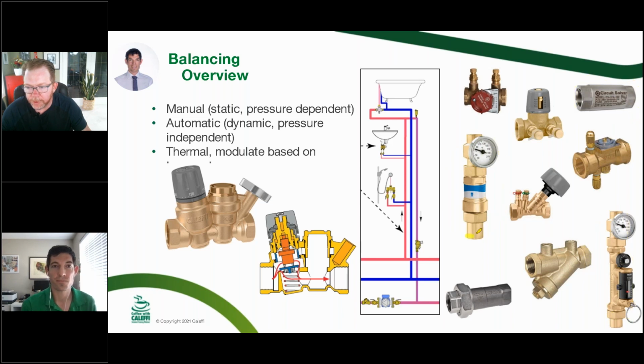Yeah, I think it's worth it. Like this one here, which is a good selection. The challenge is you're replacing a cartridge, whereas this one you've got the pull pin on it. You pull that pin, you dial your flow in, and if it turns out you're off, then you just adjust it. These, depending on which size you purchase, will dictate the flow capabilities of them. We use them for hydronic applications. We use them in heat pump applications for the ground loop side. They're definitely good controls. But yeah, that's a great statement, Max, on the labor.